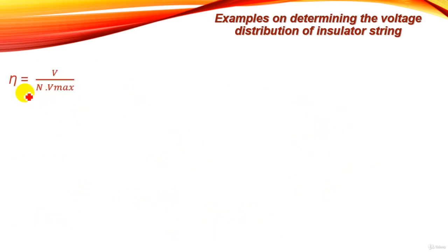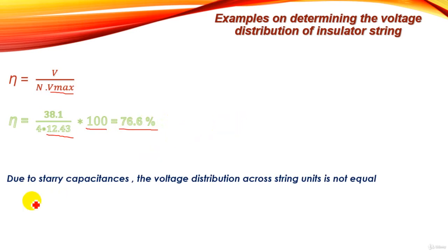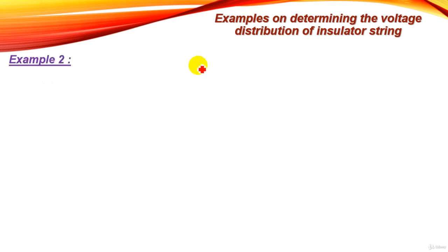Now we find the string efficiency. Eta equals V divided by (N × V_maximum). V equals 38.1 kV, N equals 4 units, and V_maximum equals 12.43 kV. So eta equals 76.6%. Due to the unequal voltage distribution across the units, the efficiency decreases. The maximum voltage is always across the unit nearest to the conductor.